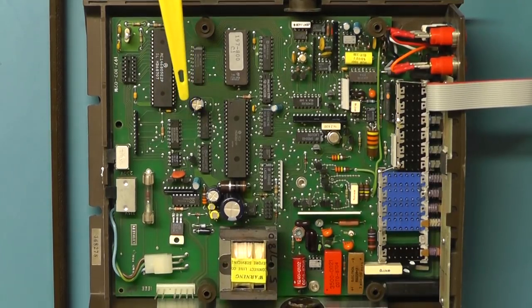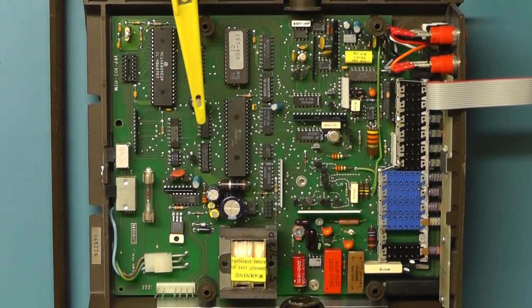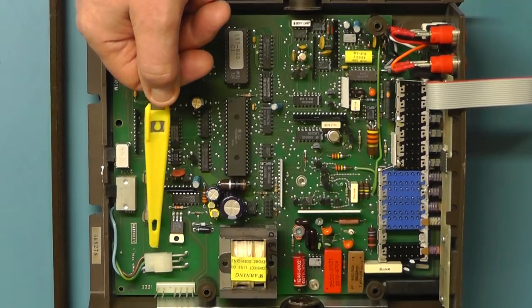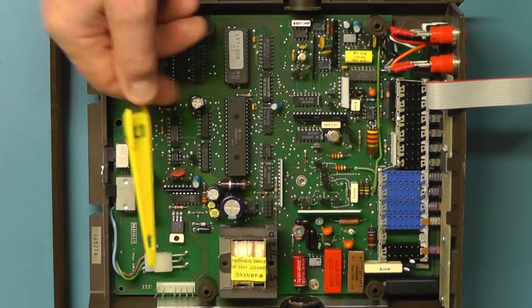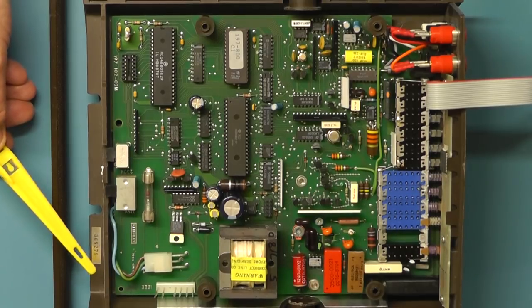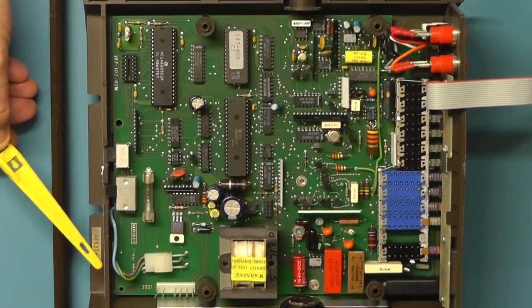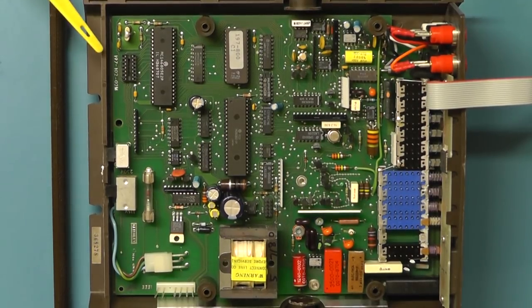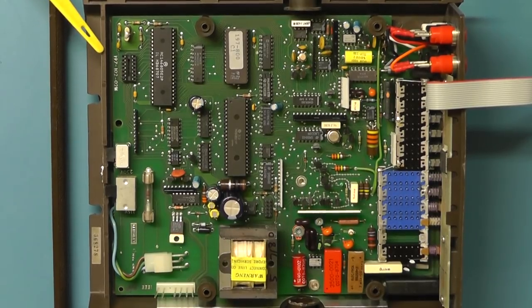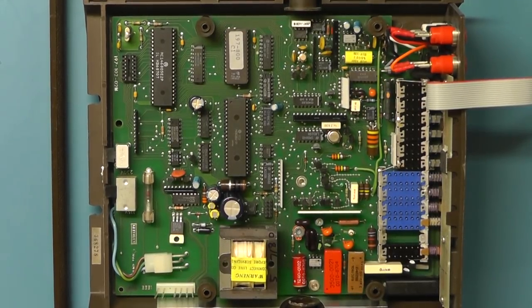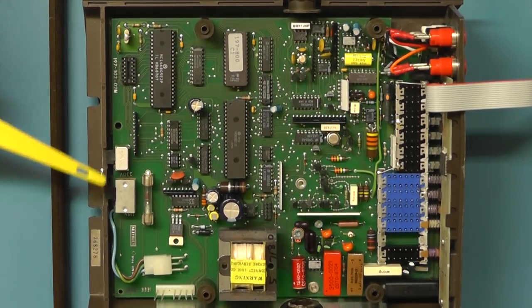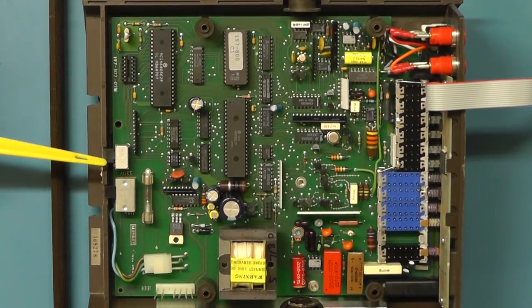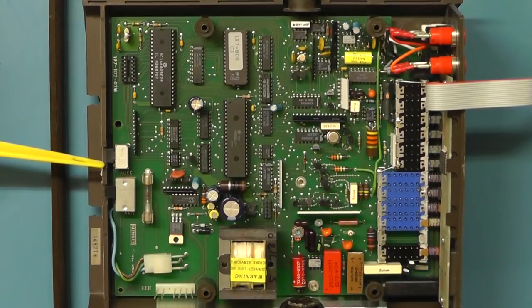As this particular meter is the 197 you'll see that the mains input lead is quite straight onto the board there whereas the 197A the A version would actually have a mains socket an IEC mains socket at the back there so that would be one of the main differences really and you'd also have a push-button switch at this side for the backlight for the liquid crystal display. At the back of the meter here we've got the mains selector switch there and the calibration switch is there next to it.